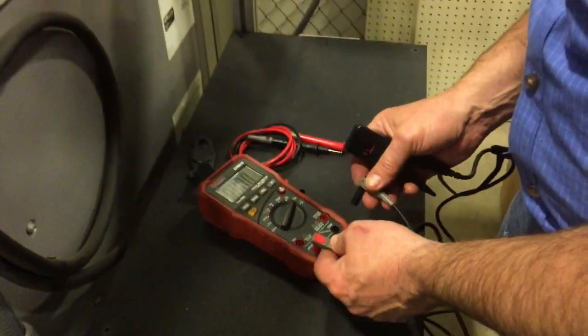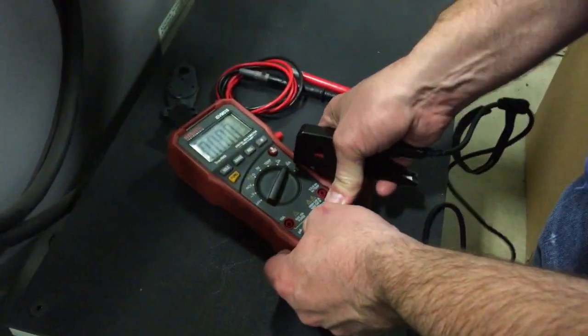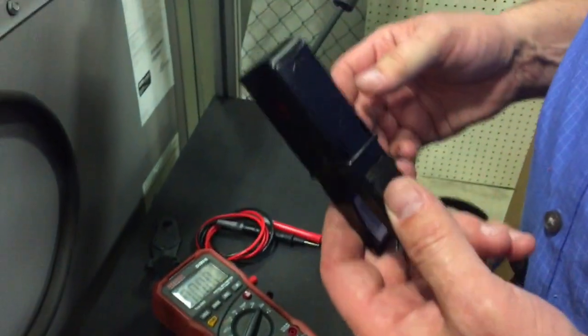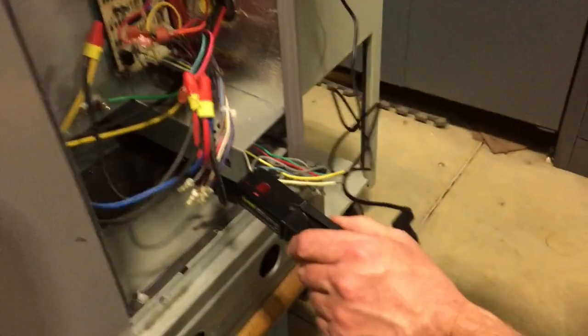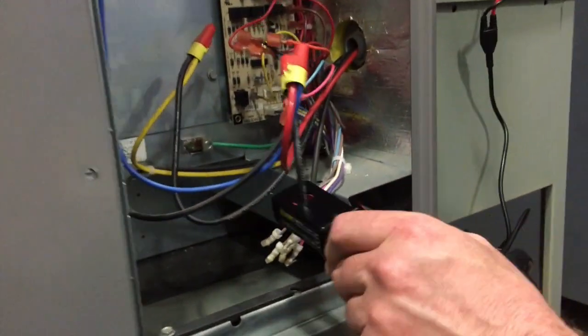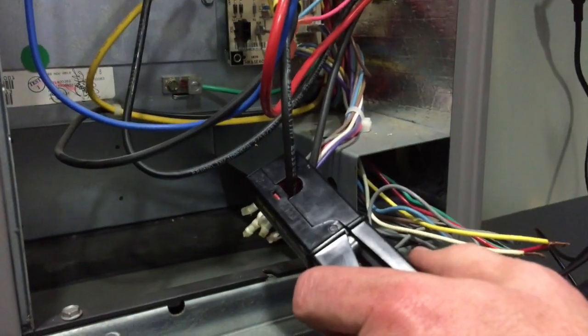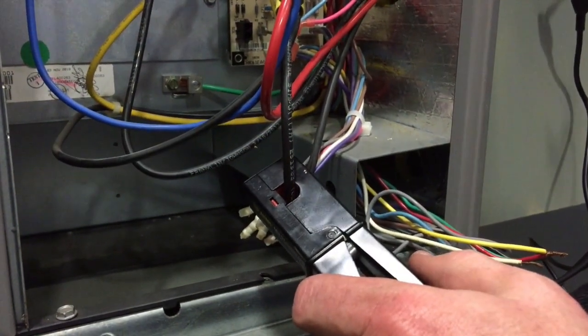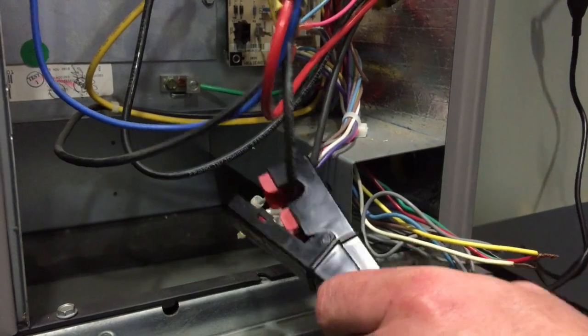In this case here, I want to use the milliamp connections, so common and milliamp, and because it's so tight in this disconnect box, what I'm going to do is close this up and actually measure the incoming power. Now again, I don't have to actually look at the meter, I can just listen for the audio tone. So there's my first current reading.